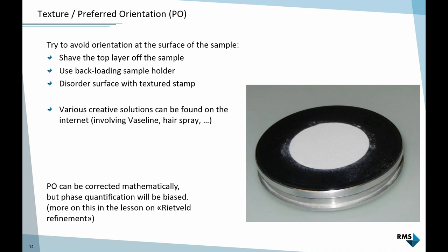There is a mathematical model we can activate during refinement to model this intensity bias. The problem is that algorithms for phase quantification don't work very well with textured samples. The more we have to model texture, the less capable the algorithms are of calculating correct phase quantities. So there's still strong incentive to avoid texture during sample preparation, though it's not always possible. We can minimize it but not completely eliminate it, then we use algorithms to model the rest.